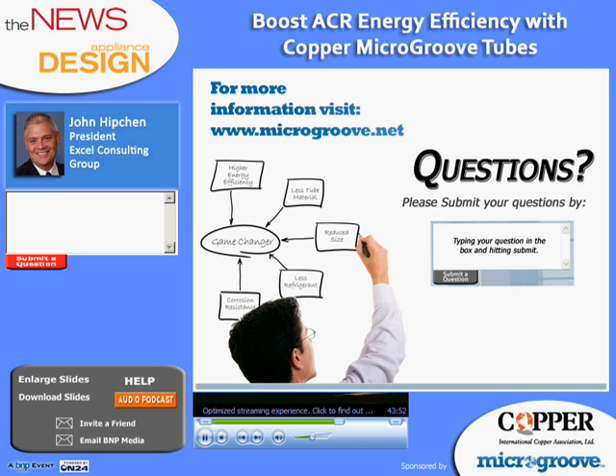Okay. Someone else would like to know, is there an aluminum microgroove? I believe there is, but I don't think it goes down in as small diameter as the copper microgroove tubes do. And aluminum being a softer material, the internal grooves are susceptible to deformation during that expansion process, during the manufacturing process. And that's something that a manufacturer has to watch if they're using aluminum internally enhanced tubes.